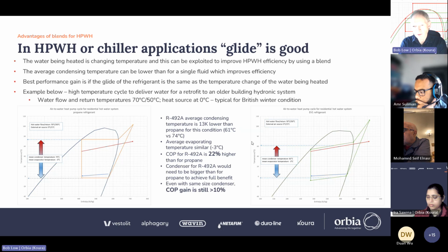So if you don't want to spend more money in the condenser, then you don't get quite as much gain, but even if you keep the same size of condenser, you will get a 10% gain in COP. So it's worth having. And if your technology is based around, say, plate heat exchangers for the condenser because it's hot water, actually adding 20-30% more area doesn't add 20 to 30% more cost, because the number of terminal points is the same, it's just some more plates in the stack. So the marginal cost is not so great.